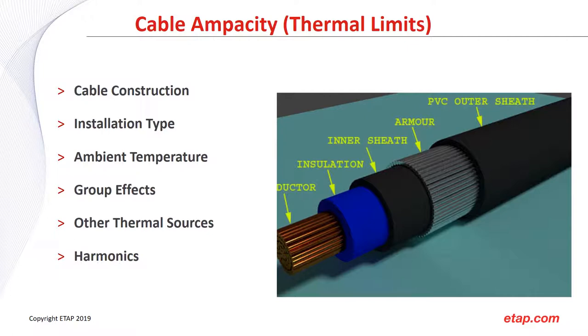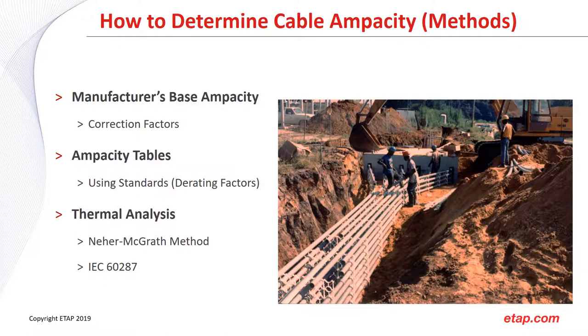Thermal limits also come from installation types — how many other conductors are running next to the cable you're sizing. Additional thermal limits include ambient temperature (Ta), group effects (how many conductors per conduit), other thermal sources such as a steam pipe running through an underground raceway, and also harmonics. If you have variable speed drives or inverters for renewable installations, those typically add harmonics, and that's something to consider.